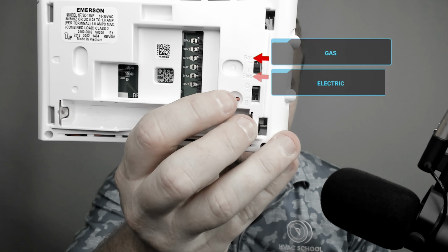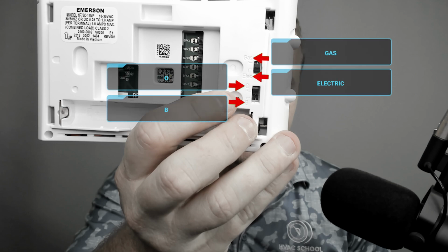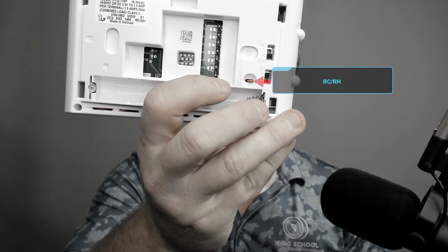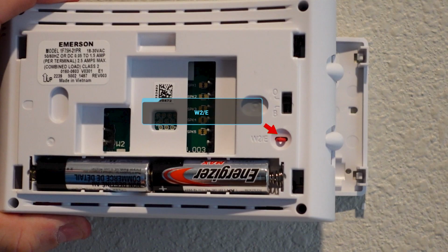So gas or electric, O or B, if it's a heat pump. And then in this case, because this is a conventional thermostat, it has an RC/RH jumper and the heat pump version, it has a W2 to E jumper in place, which is one of the most common jumpers on kind of old school thermostats you had to put in, one of the most common selectors.